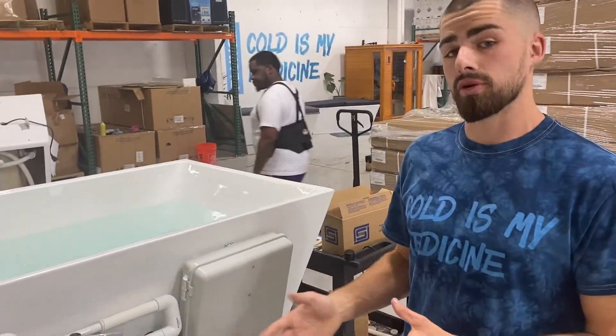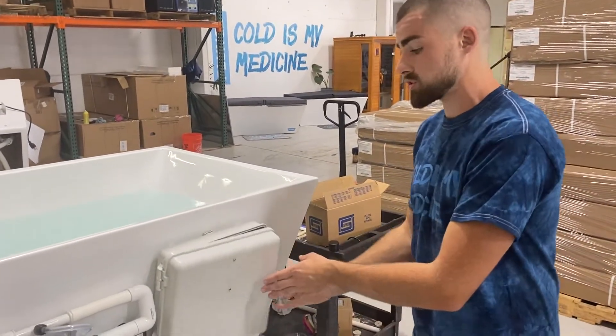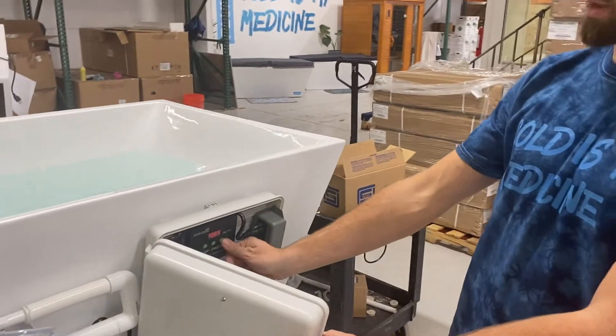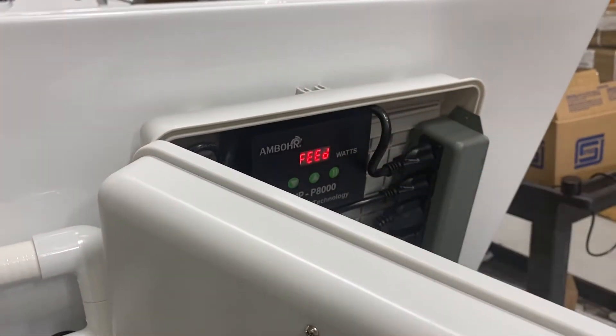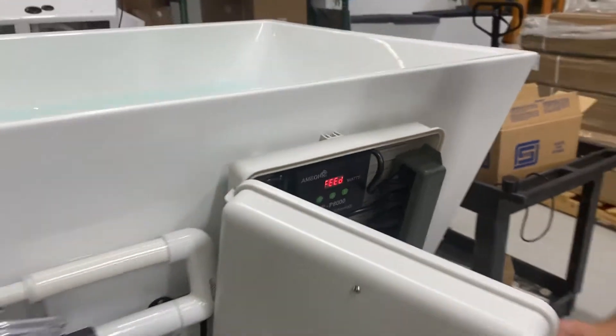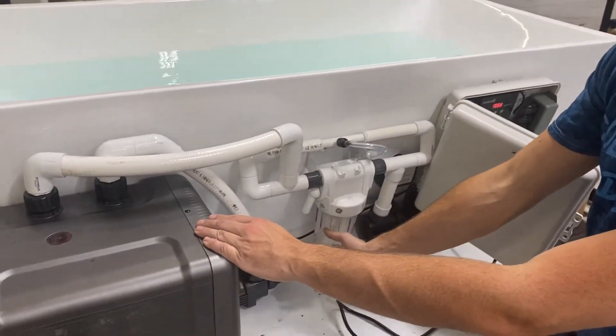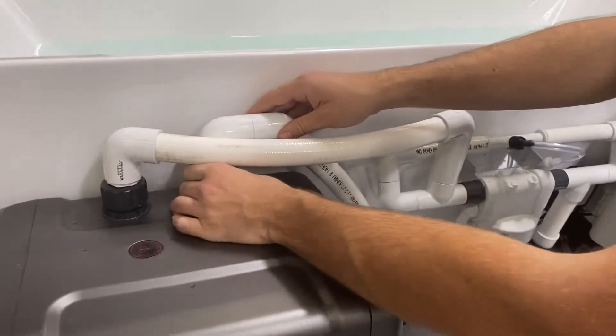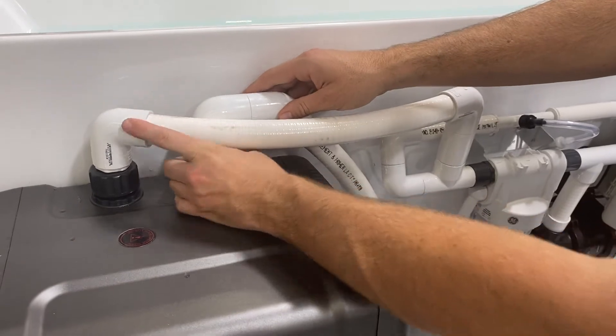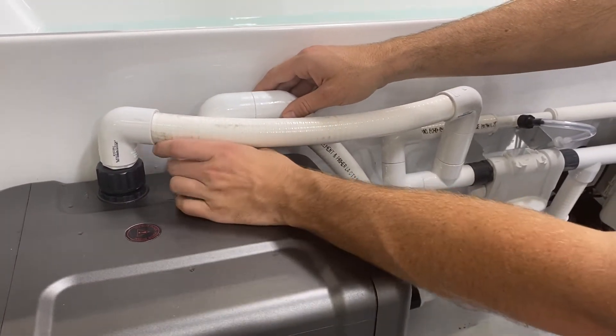If that doesn't work, then we are going to prime our pump. We first open our electric box and we press the pause button twice. We will then see FEEd on the display. At that point, we can disconnect the hose connecting our water pump to our chiller. What we do is we begin unscrewing and we will want a towel on hand and/or place our hand over this to prevent spillage.